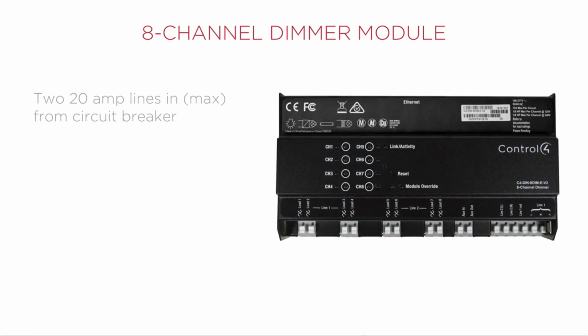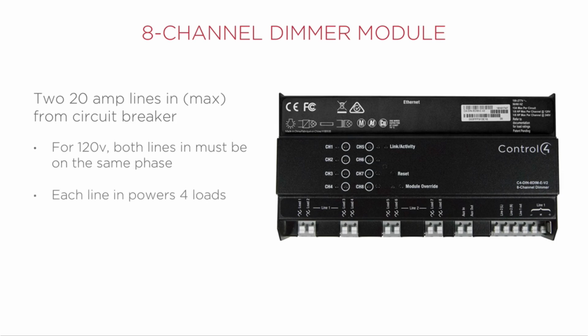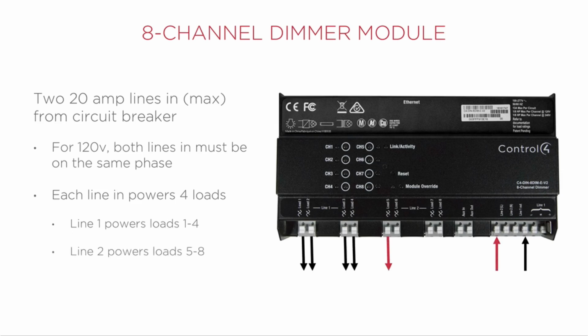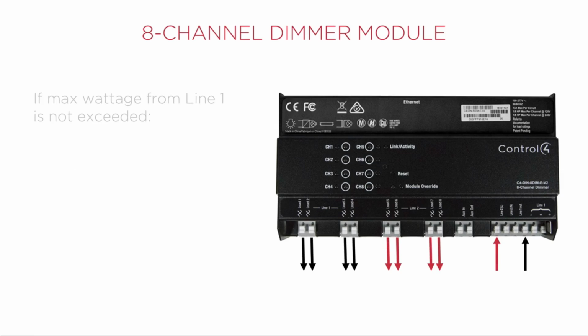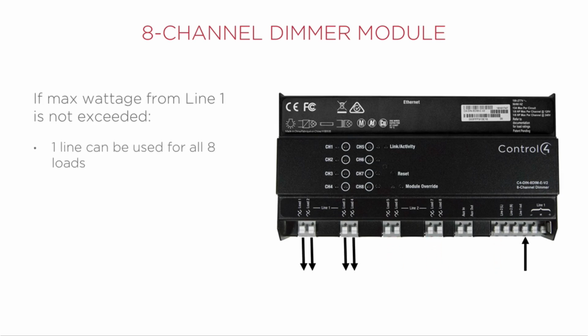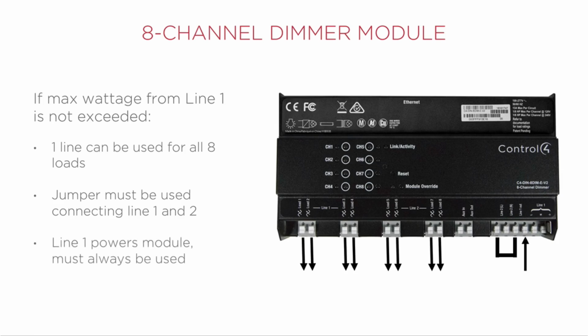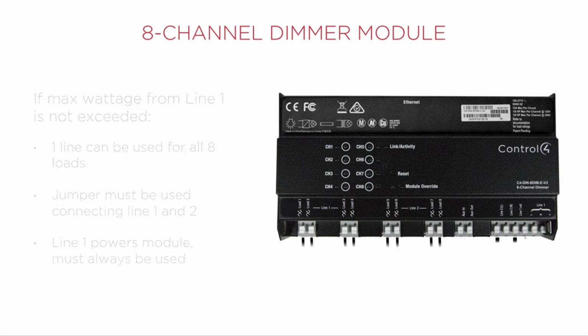The dimmer module accepts 2 20-amp lines in, maximum, from a circuit breaker. For 120 volts, both lines in must be on the same phase. Each line in powers 4 loads. Line 1 powers loads 1 through 4, and line 2 powers loads 5 through 8. If the maximum wattage is not exceeded, one line from a circuit breaker can be used for all 8 loads. A jumper must be used connecting line 1 and line 2. Line 1 in powers the module and must always be used.